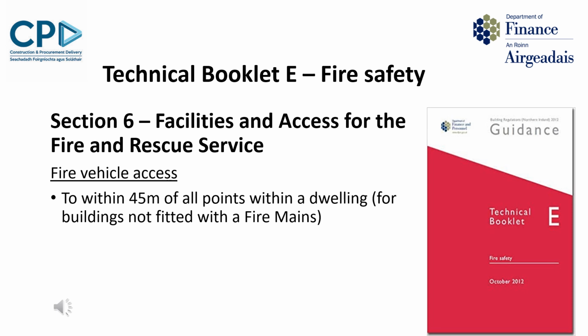The fourth item of change in Section 6 relates to fire vehicle access to buildings. TBE previously required access for pump appliances to within 45 metres of each door giving access to a dwelling. The amendment means the 45 metres has to be measured to all points within a dwelling, as opposed to the front or back door of a dwelling. It effectively means pumping appliances should be able to get closer to a building. The 45 metres is a hose route distance, and this requirement obviously does not apply to buildings that have fire mains.